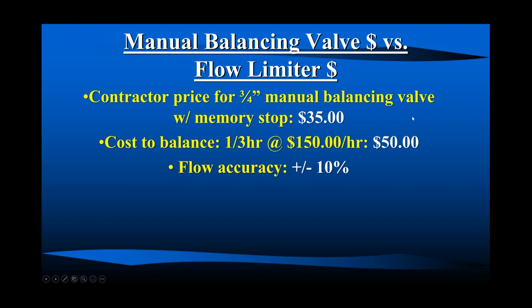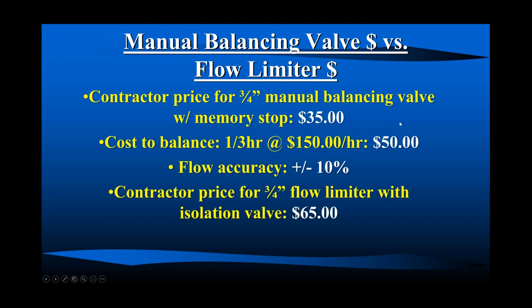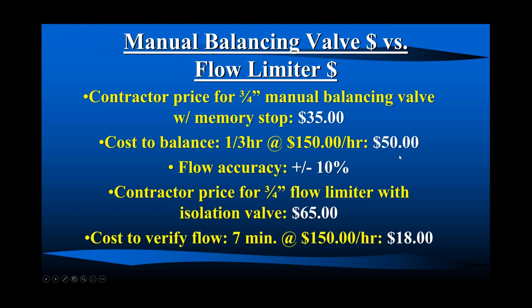Flow accuracy, some are better than others, but for argument's sake, plus or minus 10%. We'll compare that to a contractor price for a 3/4 inch flow limiter with an isolation valve, the same device we showed earlier, that was a ball valve, $65. Now you don't have to touch this thing, you can verify it if you want to. And let's say that's one touch, so it's a 7 minute ordeal. Again, the same labor allowance, so that's $18. And they're very accurate, plus or minus 5%.